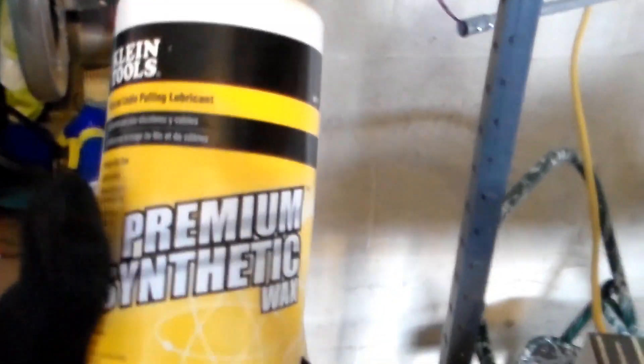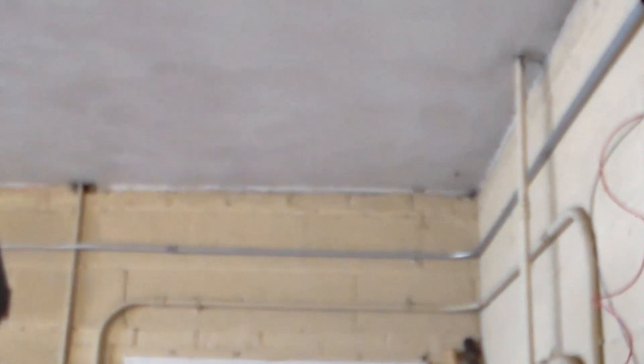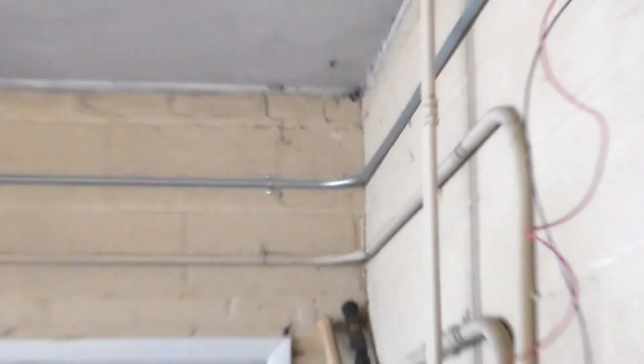Now I've started running the wiring through the conduit. I had to take the last piece of conduit off because I couldn't get the wiring through a 90 degree bend without having it on the floor. And then to facilitate that, use this stuff right here by Klein Tools called Premium Synthetic Wax. You put that on the wires before you try and run them through the conduit. And then see I took the conduit loose and I have it still attached to the wiring right here on the reel. And then after I run it through, it's already gotten through the 90 degree bend right there at that corner.